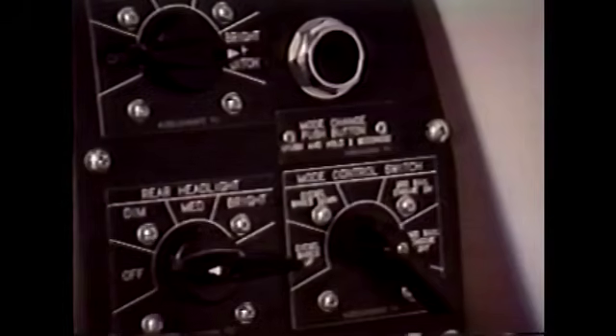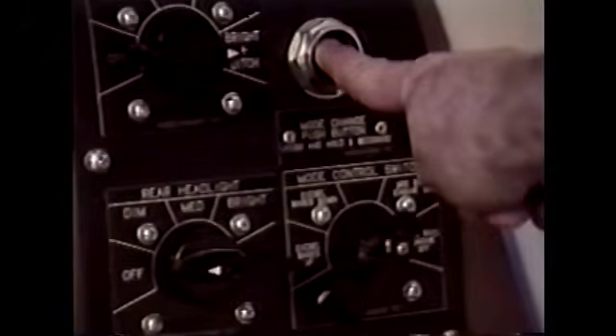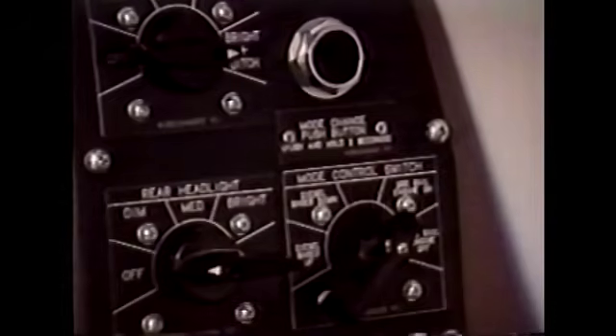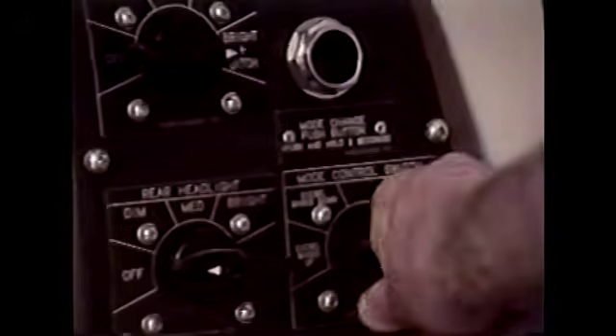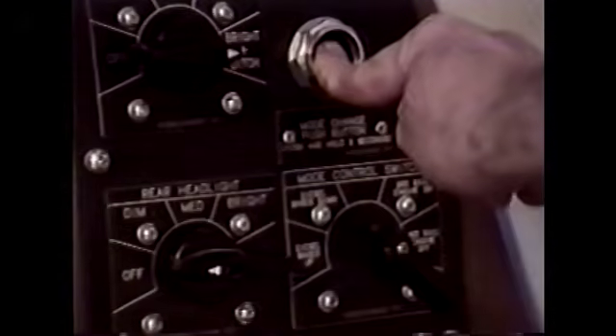When performing an initial start of a dead engine, the diesel can be started with the mode control switch in any position except the third rail diesel off position. After verifying the position of the mode control switch, you initiate the cranking process by pressing and holding the mode change push button. After the button has been held in for approximately 3 seconds, an audible alarm will sound and an engine start in progress message will appear.